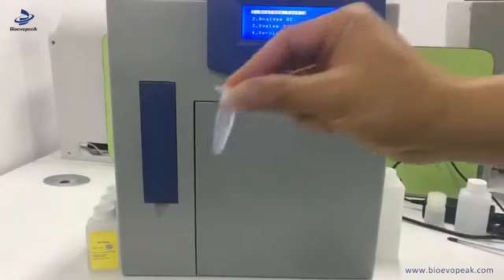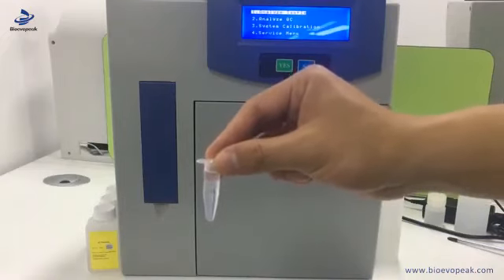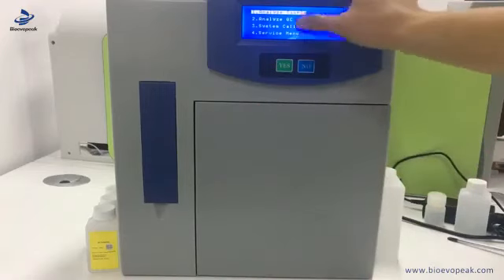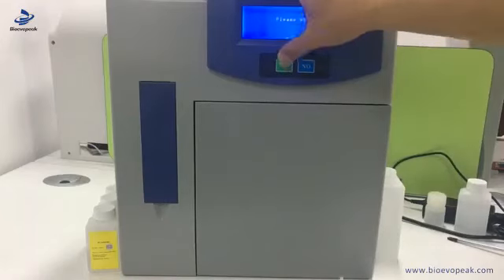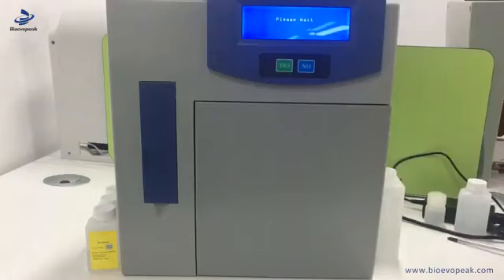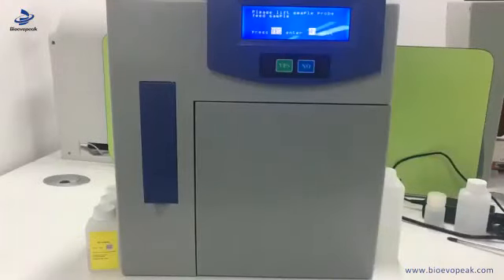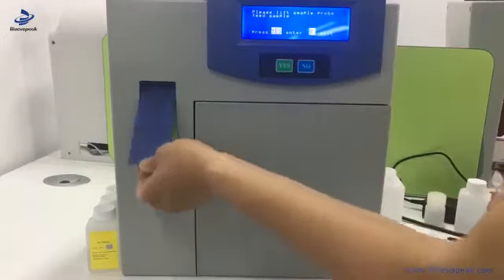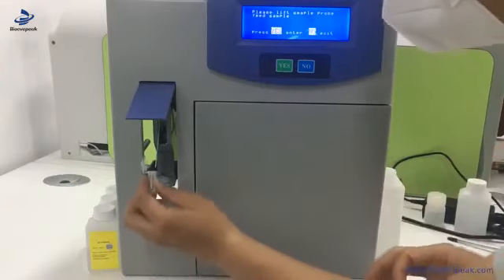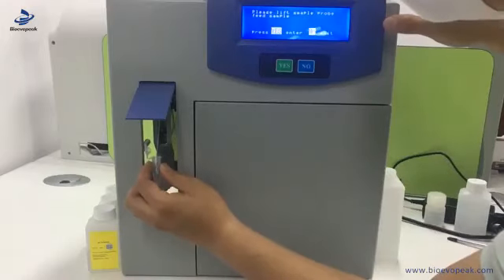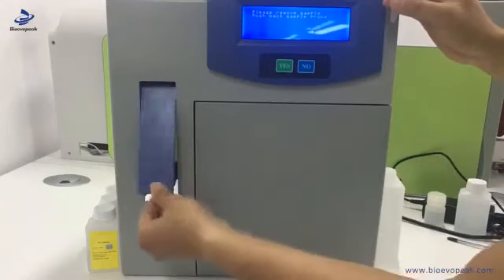Now let's test a sample. For example, this is a serum sample from the blood. Then we open it and press yes to do the sample analysis. Now we wait for a while to let the machine prepare for the testing. It will absorb some reagent from the pipeline. When it shows please lift the sample probe, we lift the probe and put the sample into the probe. Press yes. It will absorb the sample automatically. Then close the sample probe.